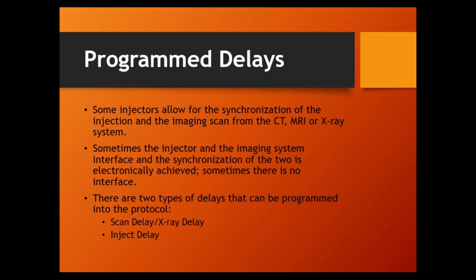Now what I do is I hit both buttons at the same time. Hit the exposure switch, hit the inject switch. The exposure switch, the image system starts its thing. The injector switch, injector delay starts counting down. And 2 seconds, bang, it starts going. Okay, so that's injector. And that's the easy one. They're both easy, but that's the easier one to do.